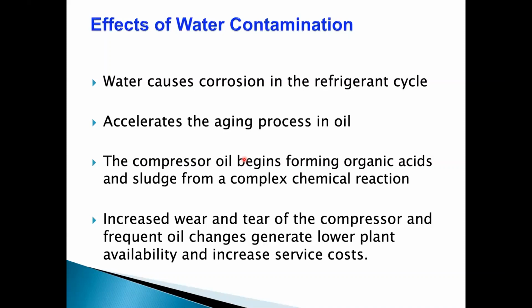So all these things contribute to the accumulation of water in our refrigeration plant. With that, it causes corrosion. When oil is mixed with water, the oil aging starts, oil quality deteriorates, and the oil starts forming organic acids and sludge in the compressors and other parts. Wear and tear of the compressor goes up, the oil needs to be changed frequently, and it increases service and maintenance cost.